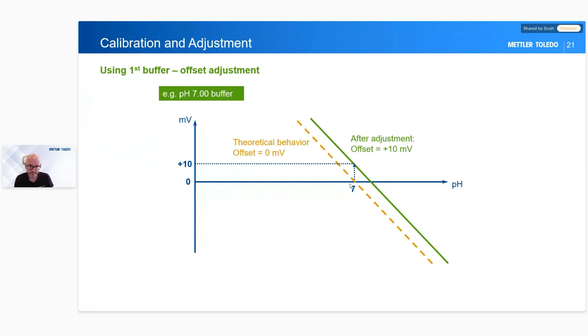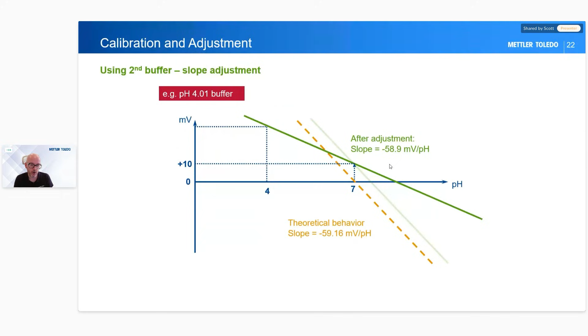So we've got a 2-point adjustment here now, and this slope has moved. Once we've done this, we've given an offset and then a slope. And this slope, we were meant to have 59.16, which is what I had on the slides before. But in reality, we've actually got 58.9. When we do this, in meters we normally write it as a percentage. So in this case, the difference between these two is about 0.5%, so it would be 99.5%. And that's generally how it's written in a pH meter. When it comes up, it'll give you the slope as a percentage and then the offset. And that's basically what we're doing when we're calibrating.